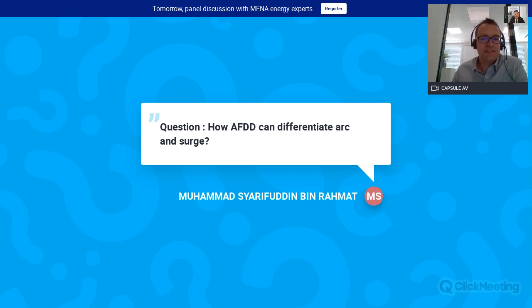Oh, we have a first question. How can AFDD differentiate arc and surge? I think I will answer this, Luke. Yeah, you can. These are very different phenomena. A surge is at the beginning a link to the voltage. It can also be a surge of current, but it's very short in time. A surge is a very short phenomenon, whereas an arc fault is something that will last for a few half cycles. So the algorithm is able to detect the difference between both phenomena.